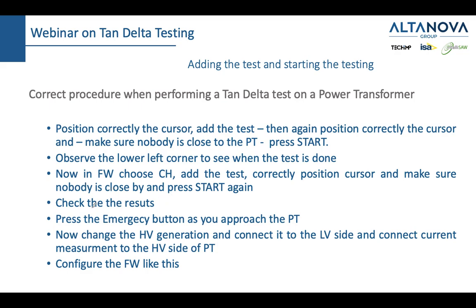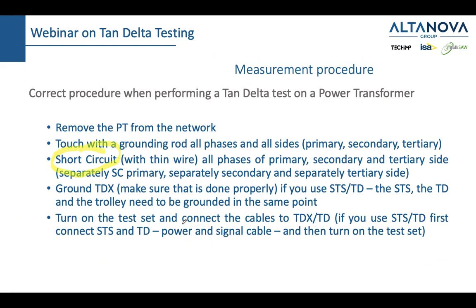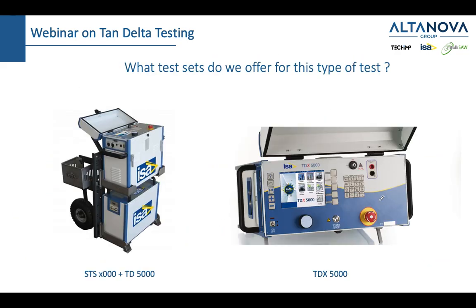Then you would press the emergency button. The emergency button is a very nice mushroom type red button, which is this one here. We also have it here. And this button is important because, of course, nobody is going to intentionally press start when somebody is on the transformer, but nobody knows if something like that will happen accidentally.